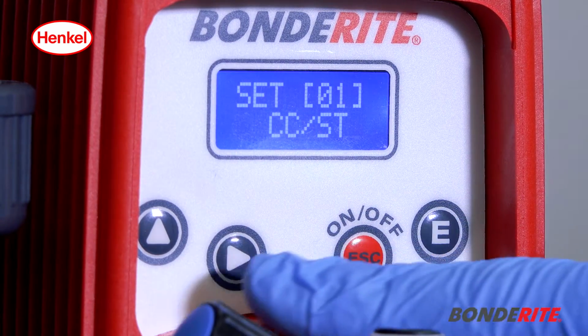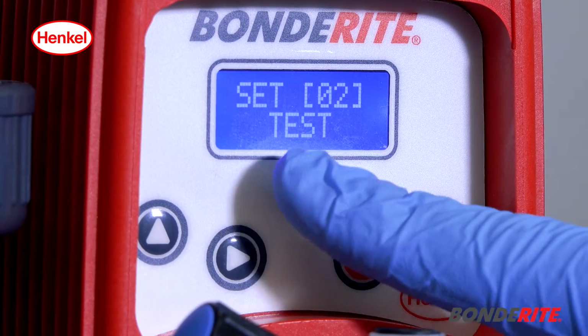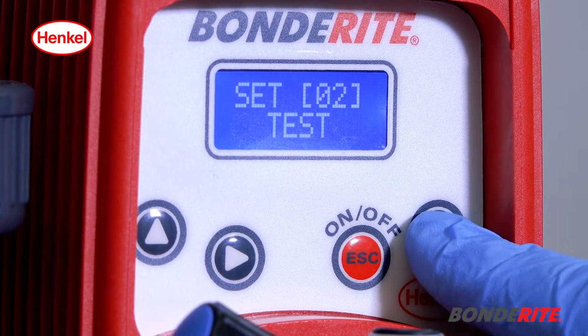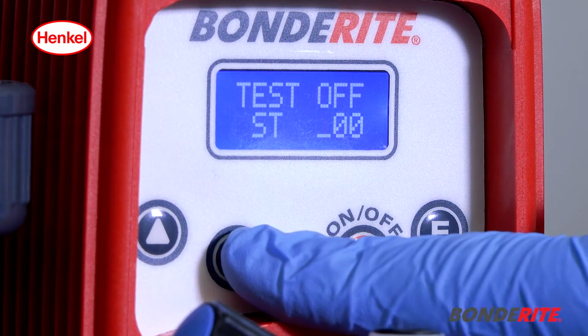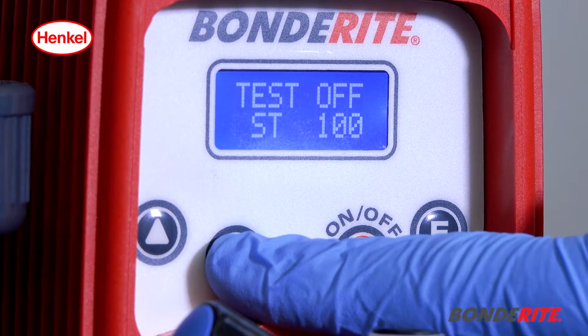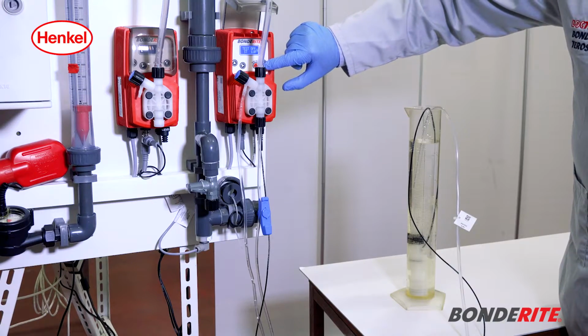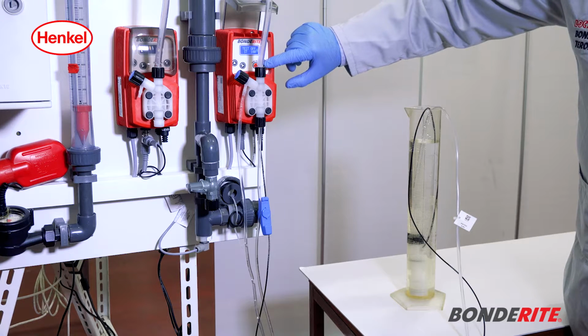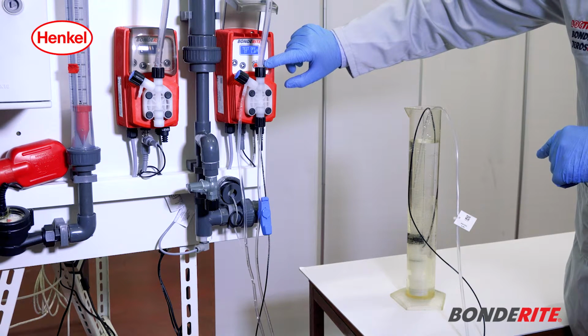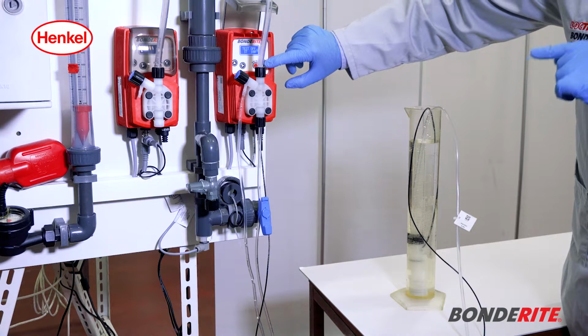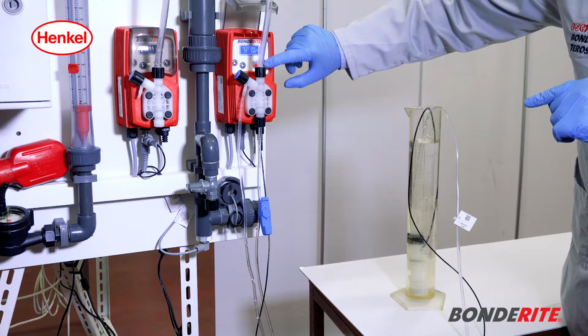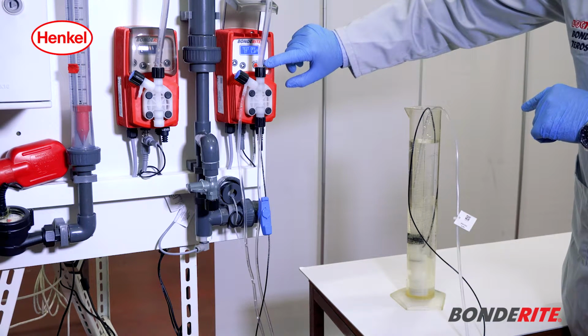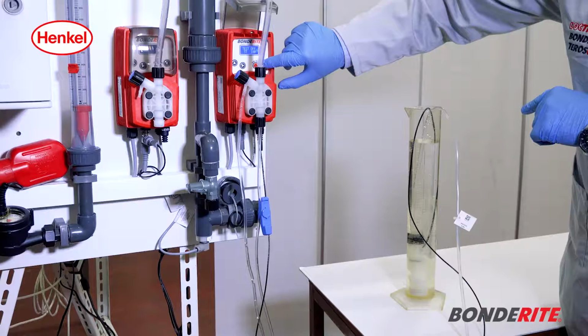Press Enter, then press the up arrow until you arrive to Test. Press Enter and press the right button to set 100 strokes. Finally, press Enter. The pump will start withdrawing and will count 100 strokes backwards. At the end of the cycle, we'll take into account the liquid volume the pump withdrew.